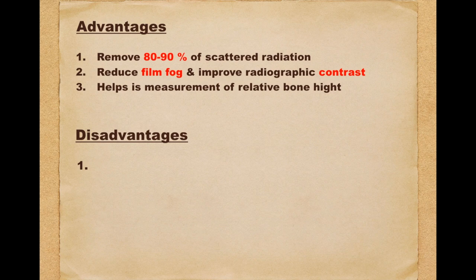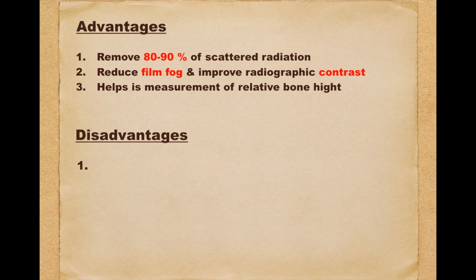Now some disadvantages. The exposure time has to be increased as the lead strips absorb the X-ray photons and reduce the number of incident photons. So grid should be used only when improved image quality and high contrast is necessary.